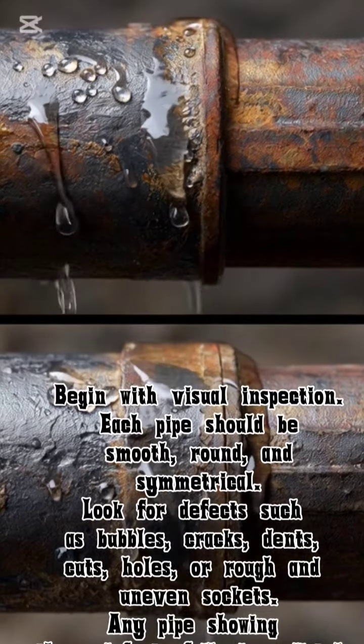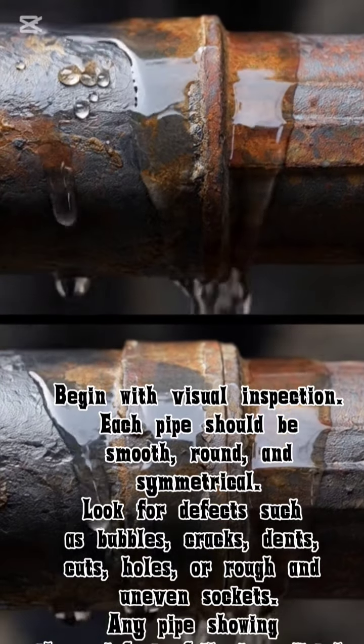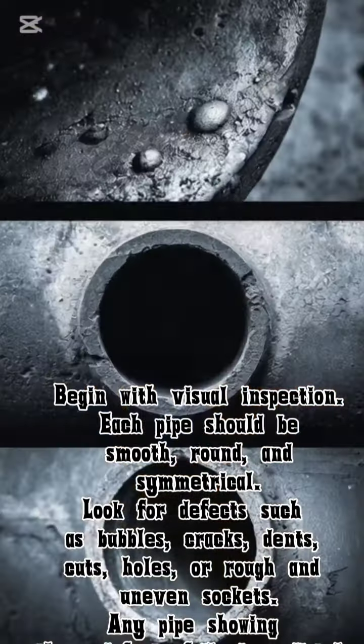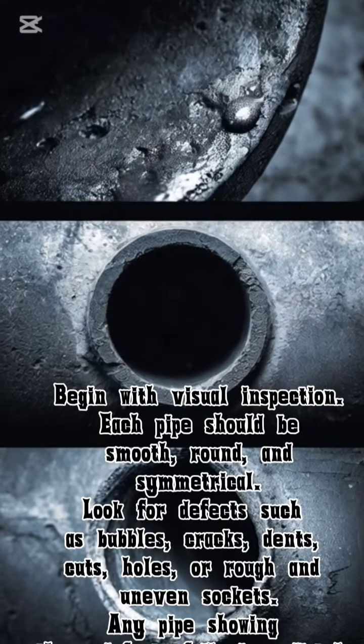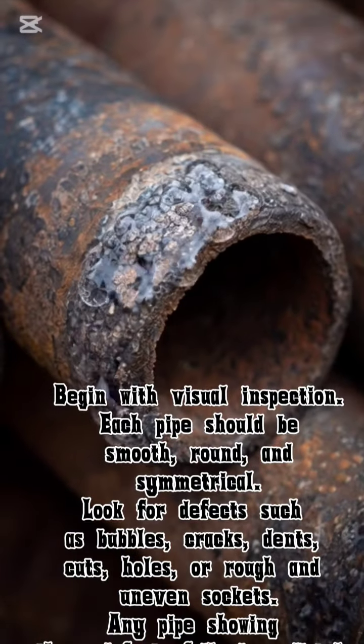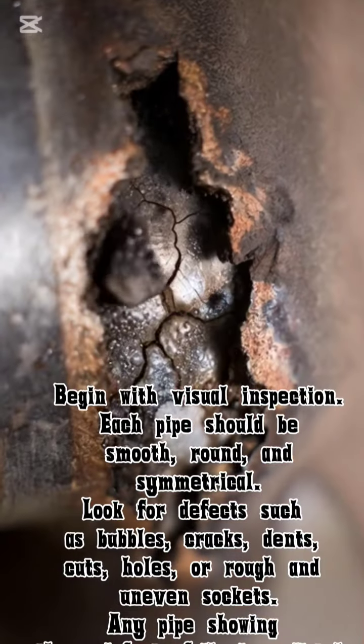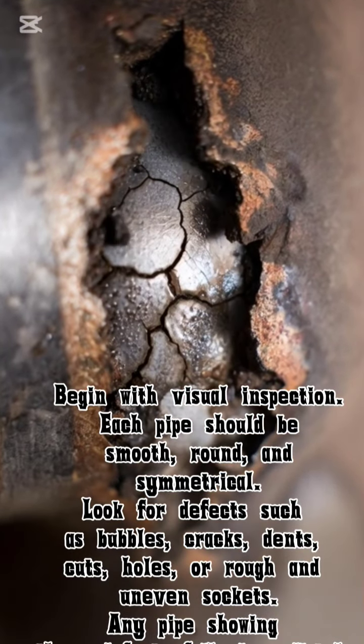Begin with visual inspection. Each pipe should be smooth, round, and symmetrical. Look for defects such as bubbles, cracks, dents, cuts, holes, or rough and uneven sockets. Any pipe showing these defects fails immediately.